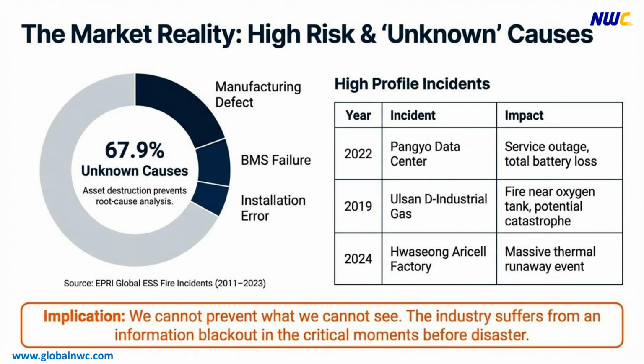Approximately 68% of ESS fire incidents are classified as undetermined causes due to the complete destruction of assets. This makes root cause analysis virtually impossible, increasing systemic risk across the entire industry. Large-scale incidents, such as the recent Aricell factory fire, clearly demonstrate how devastating an information blackout can be when early warning signs of thermal runaway fail to be detected. Ultimately, risks we cannot see cannot be prevented.